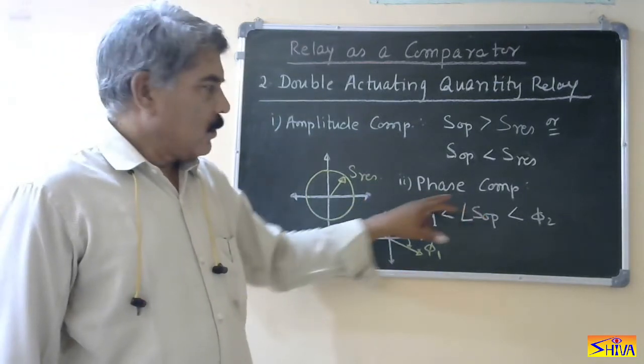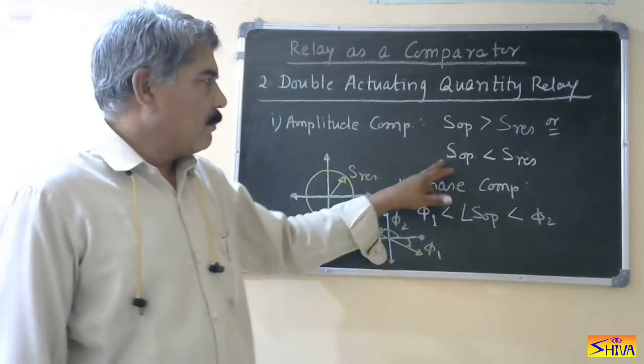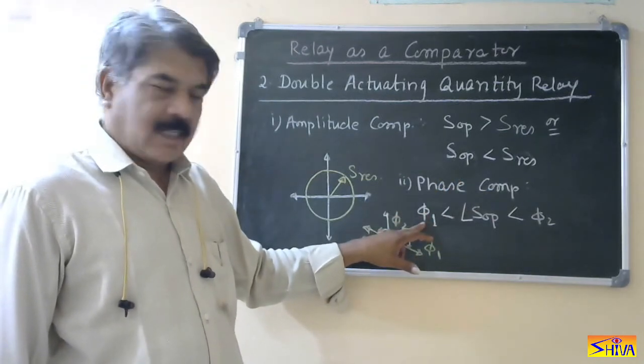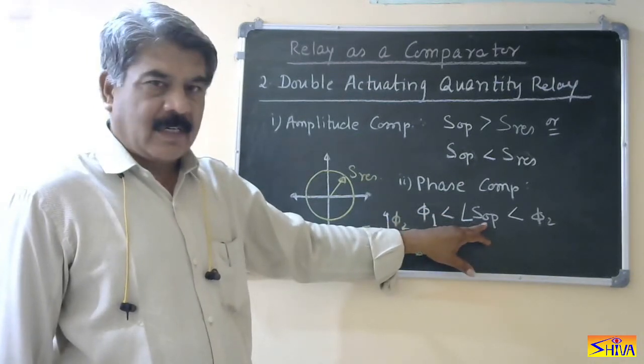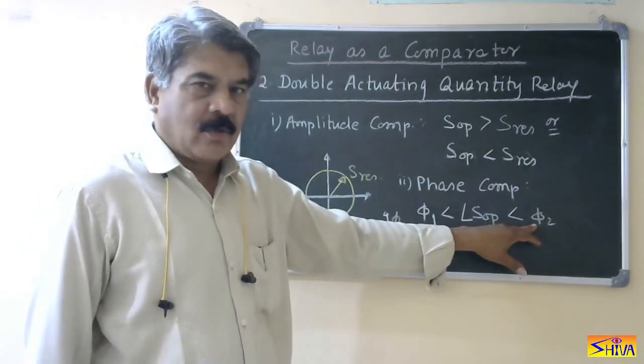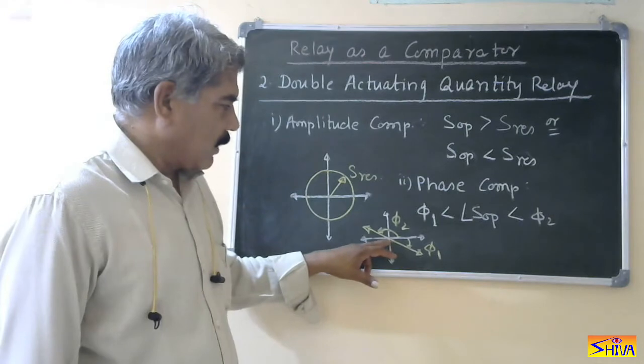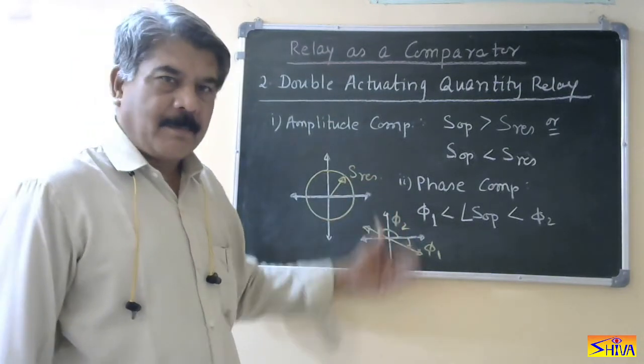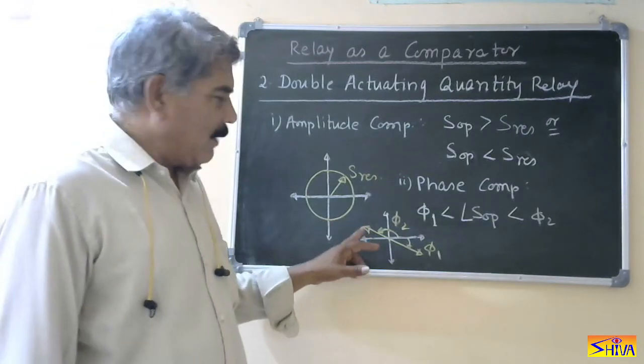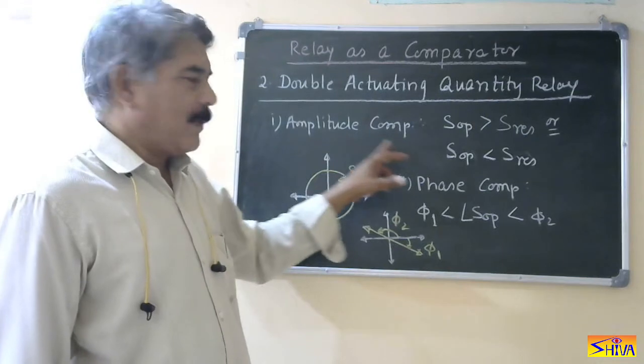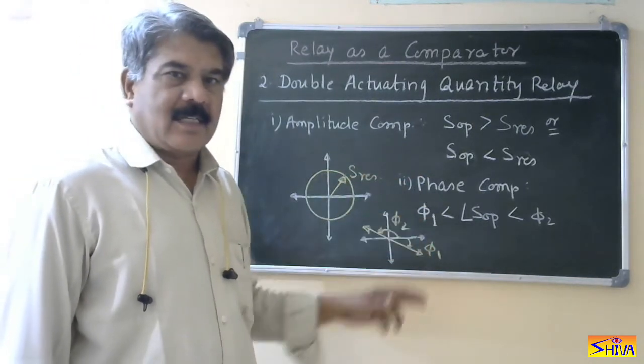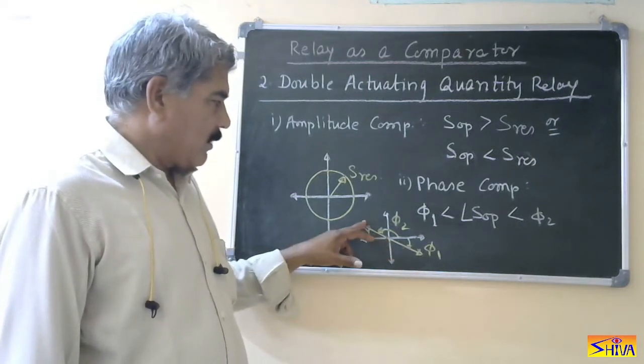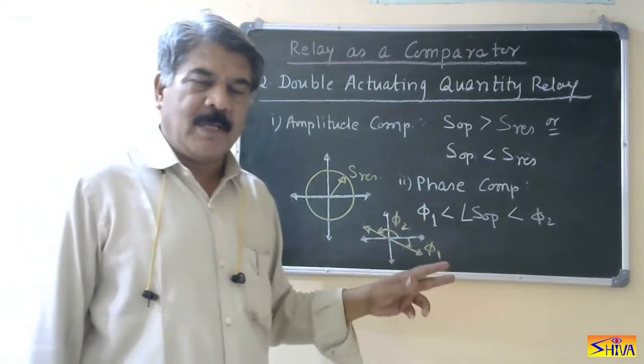Next is the phase comparator. Phase comparators compare only the phase angle of both the restraining quantity and the operating quantity. The condition is: the phase angle phi-1 is less than the phase angle of the operating quantity with respect to the reference quantity, which is less than phi-2 — then the relay will operate. In the complex plane, considering phi-1 and phi-2, the region above this range is the operating region. An example is the directional relay. So the directional element has a straight-line characteristic. If it is an amplitude comparator, the characteristic is a circle; if it is a phase comparator, the characteristic is a straight line. If the addition of the two angles is 180 degrees, it is a single straight line; otherwise, there is one straight line in each quadrant.